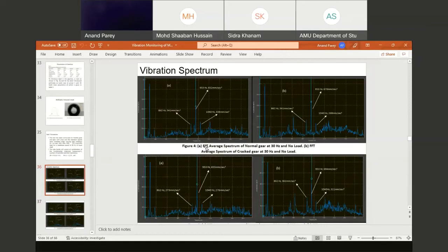These gear mesh frequency and sidebands were observed for various load conditions. A is the spectrum of the healthy gear at no load, and B is the cracked gear. So the left side figure is for healthy gear and the right side is for cracked gear at various loads. This one is for no load, with speed constant at 30 hertz.